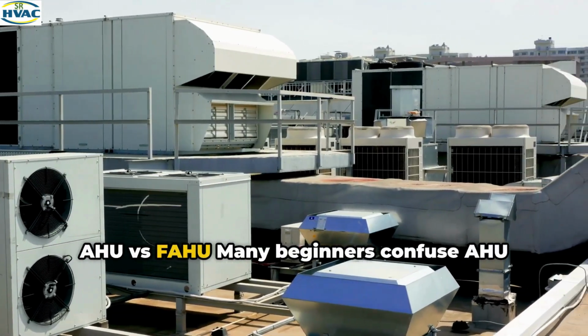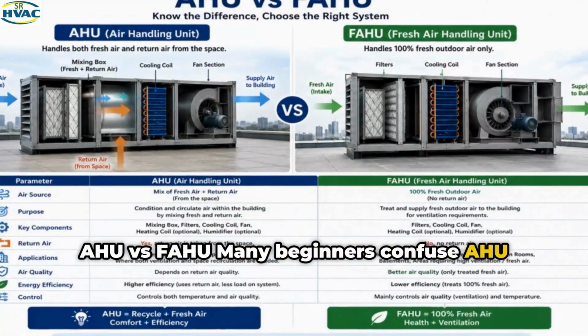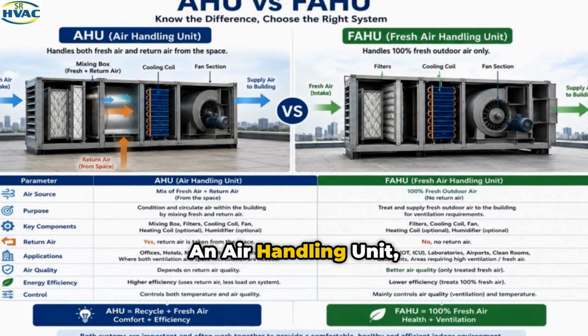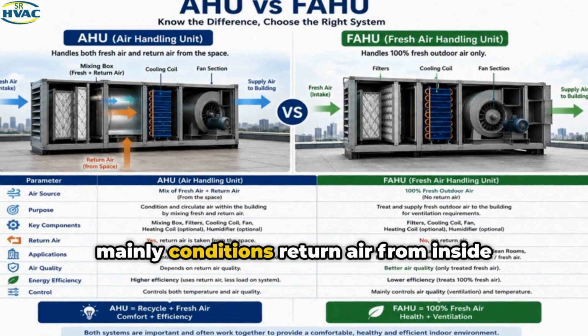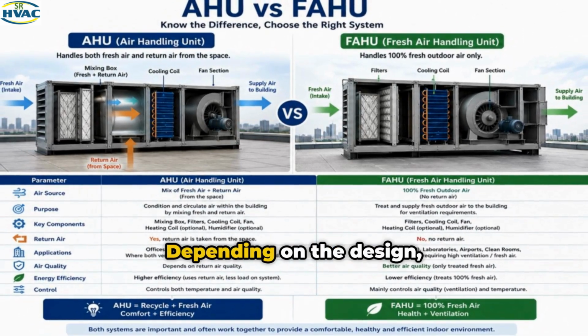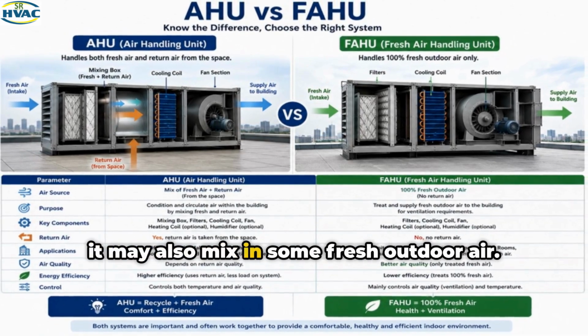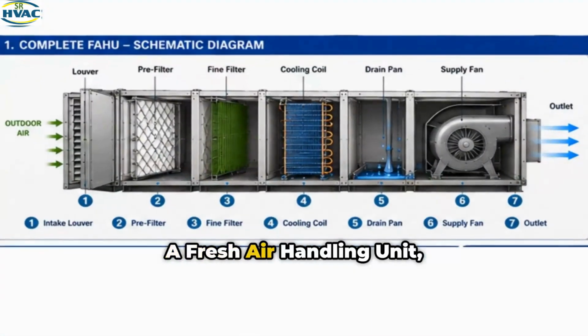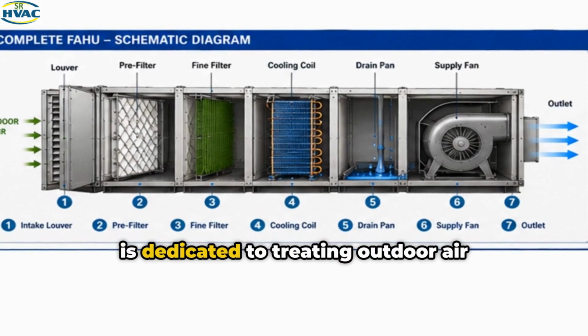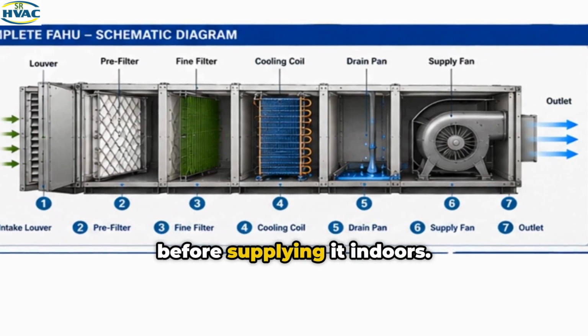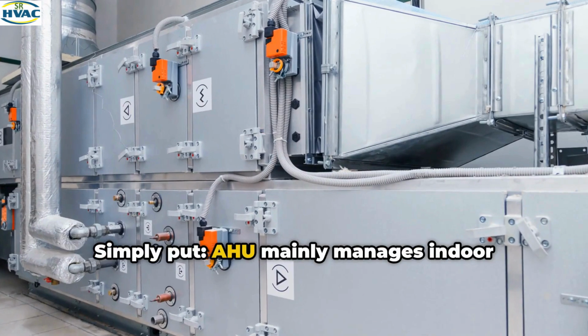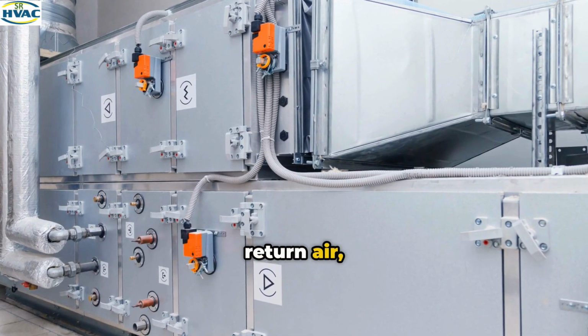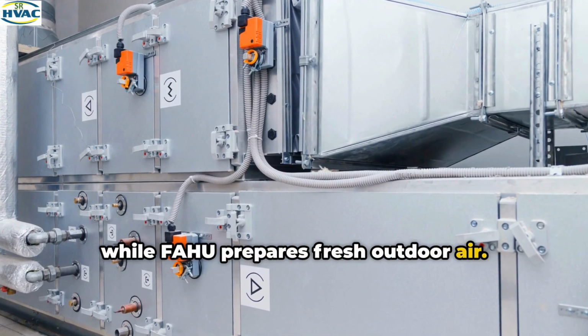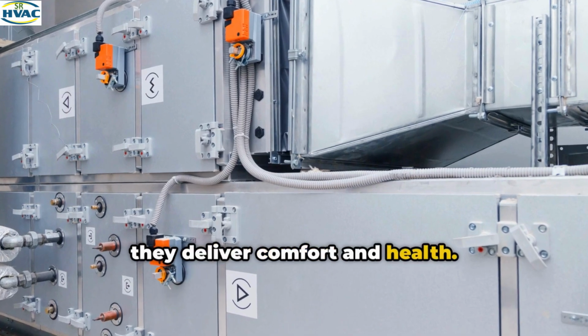AHU versus FAHU. Many beginners confuse AHU and FAHU. An air handling unit, or AHU, mainly conditions return air from inside the building. Depending on the design, it may also mix in some fresh outdoor air. A fresh air handling unit, or FAHU, is dedicated to treating outdoor air before supplying it indoors. Simply put, AHU mainly manages indoor return air, while FAHU prepares fresh outdoor air. Together, they deliver comfort and health.